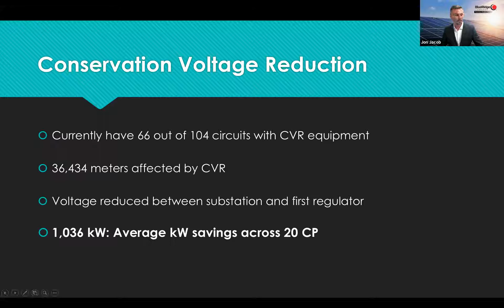Basically, standard operation is 125 volts. We drop that to 121.5 or 122 during CVR. And that 3% voltage reduction equates to about a 2% load drop for us.